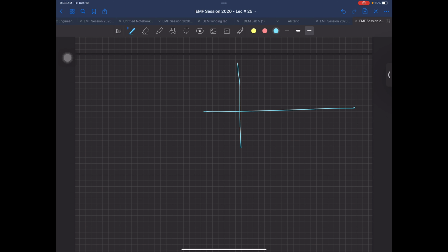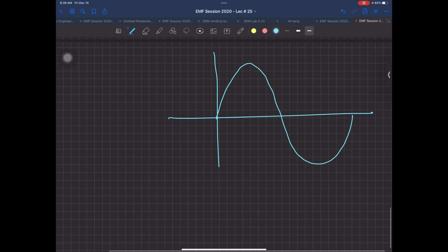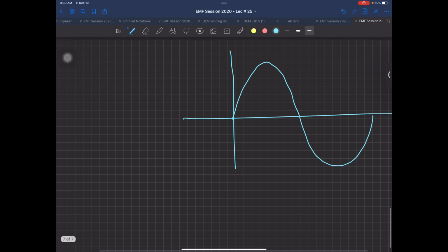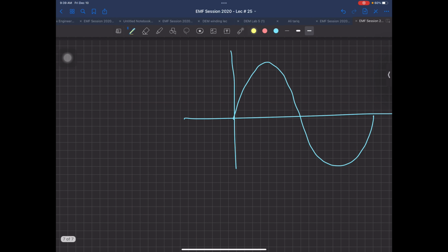You are actually having, let me just give you an idea, a sine wave applied to your fan. Okay? There is a device, I'm not going to go into very much detail, called a Thyristor. The Thyristor controls the waveform: this yellow part is going to go towards the fan, or it is going to turn on at an angle.